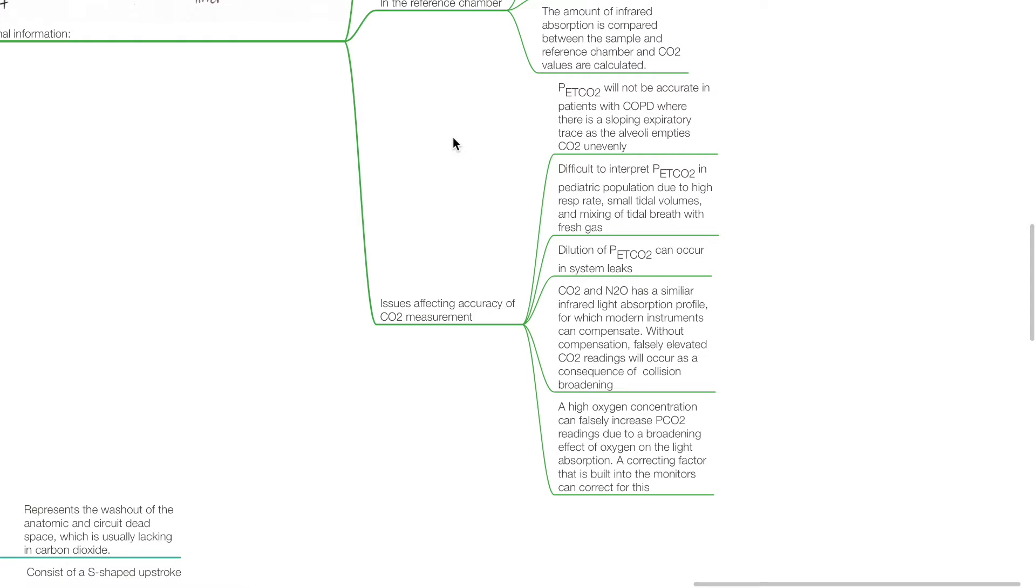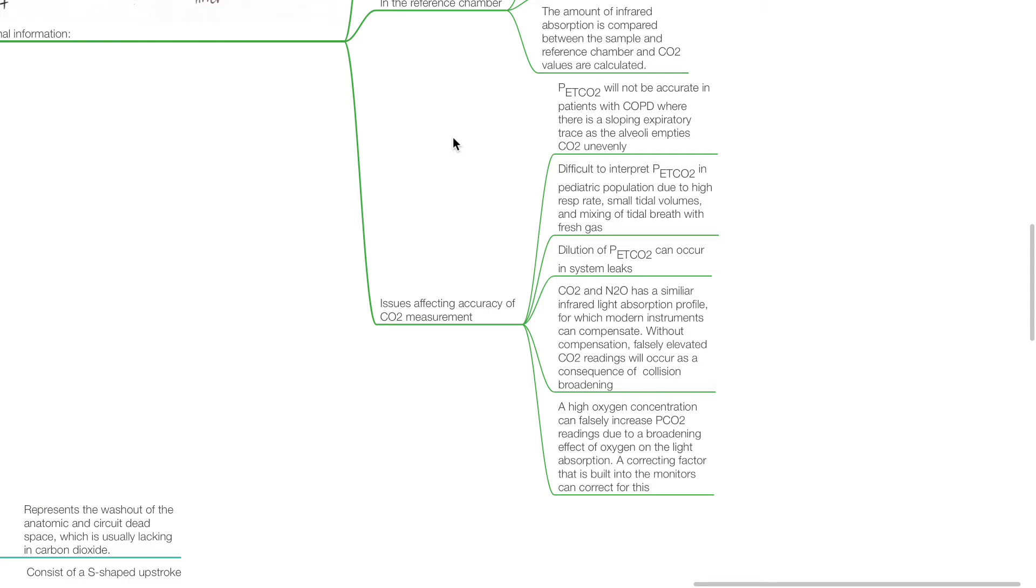CO2 and nitrous oxide have a similar infrared light absorption profile for which modern instruments can compensate. Without compensation, falsely elevated CO2 readings will occur as a consequence of collision broadening. A high oxygen concentration can falsely increase pCO2 readings due to a broadening effect of oxygen on the light absorption; a correcting factor built into the monitors can correct for this.